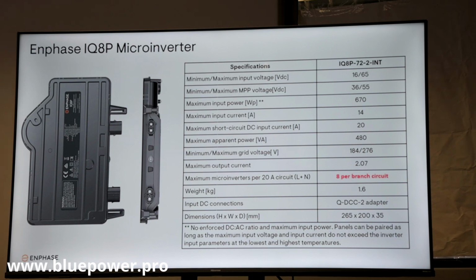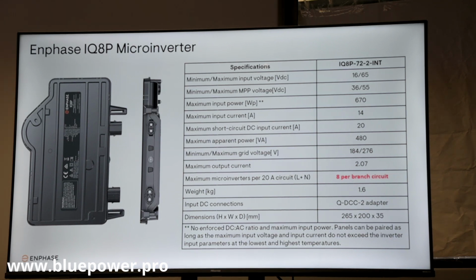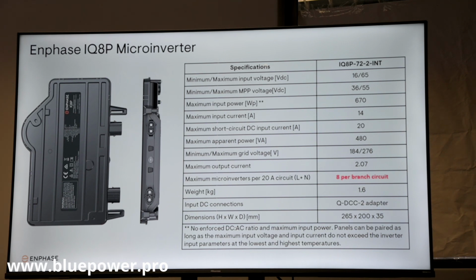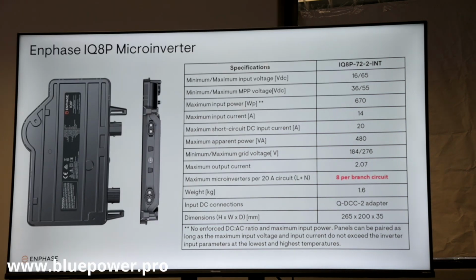Now you can configure these microinverters to either be on a single phase or a three phase. So on a three phase run, one phase, your L1, L2, L3. Your L1 in this case takes a maximum of 8. So when you plug in your first microinverter, that will be L1, your second plug will be L2, your third plug will be L3. And so you actually build up the branch, but we'll have a look at it just now.